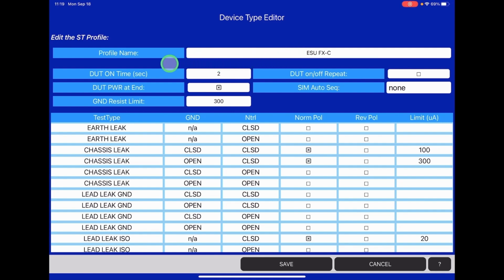It needs us to do electrical safety testing for a variety of things, so we need to program some settings. Here is the device under test, the DUT on time. How long do we want to perform each electrical safety test before we advance to the next one? Here it's defaulted for 2 seconds, which is a good time to do each individual test that's required. Next is DUT on-off repeat. And this is whether you want to repeat the safety testing twice, with the device under test off and again with it on. For the Force FXC, we do not need to repeat it twice, just with the unit on.